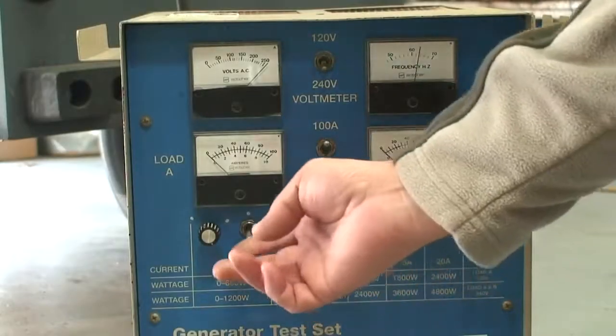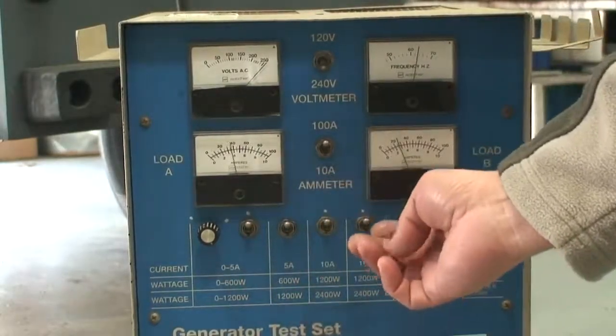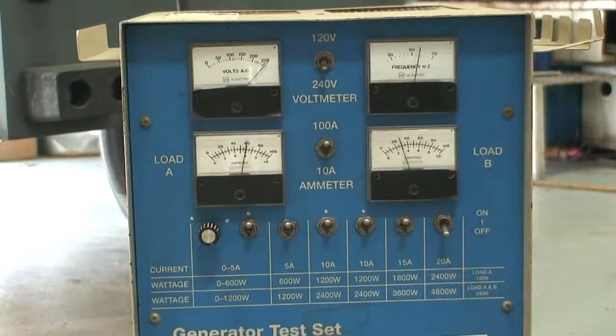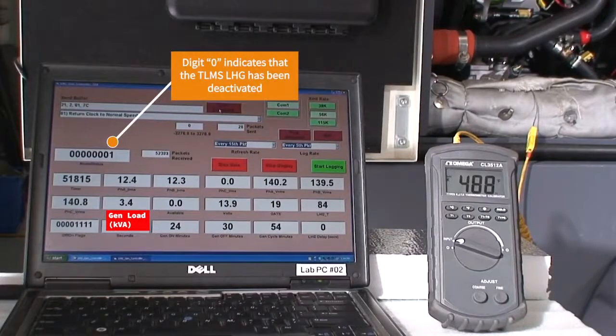10 kilowatts of resistive load is applied to the generator. Note that when the load bank is turned on to 10 kilowatts, the digit in the status bar goes to 0, indicating that the load management system has been deactivated. You can also see in the generator load field on the PC, it is now showing 10.4 kVA.